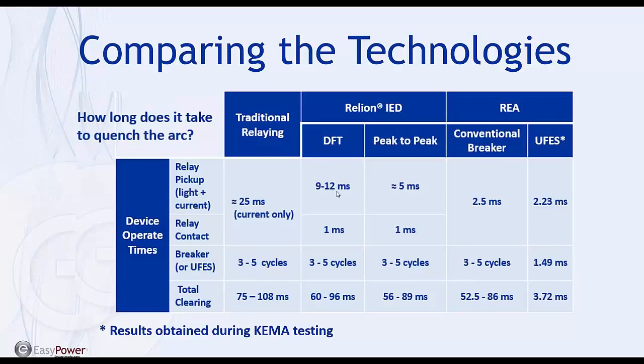Depending on the measurement mode, you can even cut it down a lot more, to just twice the time it takes the REA to operate. So really, when you look at it, you've got the 25 cut in half with DFT measurement mode, and then cut in half again with peak to peak. Even though it's not as accurate, now you're starting to get very fast. And then the conventional REA is of course the very fastest. With the ultra fast earthing switch, you don't have to depend on the breaker. So that's all of your times here, and these times are basically what we're going to use to model the response times in the EasyPower arc flash study.